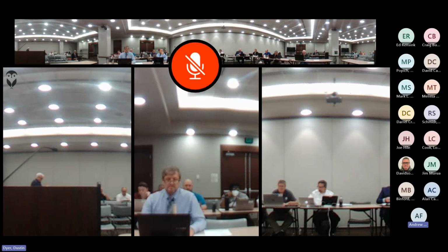Here we go. The code mandates that repair garages used for the repair of commercial trucks or buses exceeding 5,000 square feet be provided with an automatic sprinkler system. This requests installing a fire alarm, smoke detection, and heat detection system in lieu of the sprinkler system. This is meant just due to the scale of this particular project.